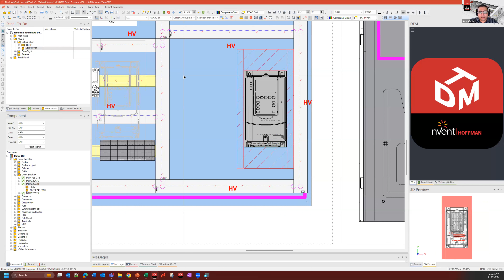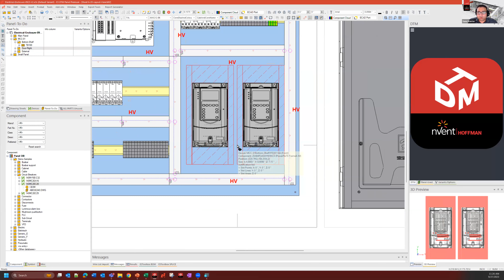My VFD — similar concept, very easy to manipulate items. I can just line them up and they lined up. This red area is a keep-out area for your VFD, for airflow and cooling. It's there, and you need that for the VFD — otherwise you're going to do a smoke test pretty quickly.